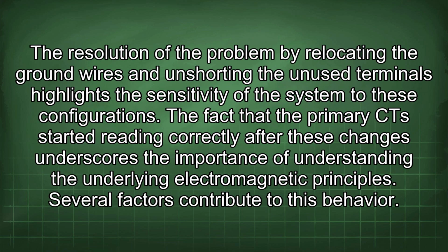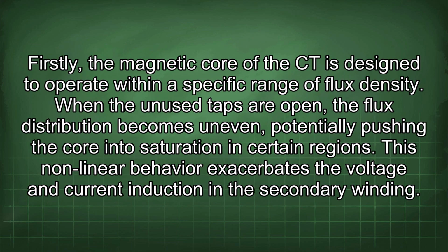The resolution of the problem by relocating the ground wires and unshorting the unused terminals highlights the sensitivity of the system to these configurations. The fact that the primary CT started reading correctly after these changes underscores the importance of understanding the underlying electromagnetic principles. Several factors contribute to this behavior. Firstly, the magnetic core of the CT is designed to operate within a specific range of flux density. When the unused taps are open, the flux distribution becomes uneven, potentially pushing the core into saturation in certain regions.